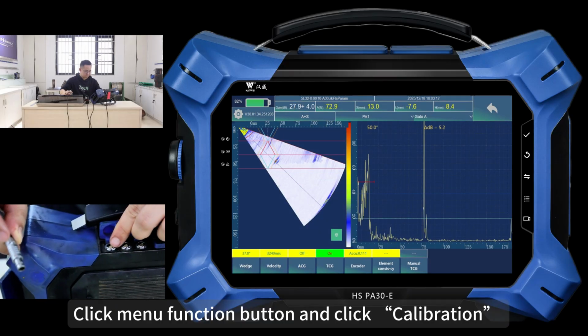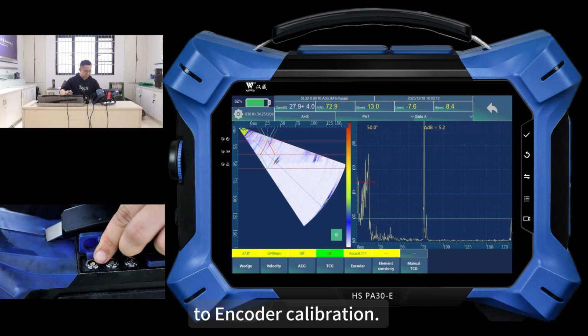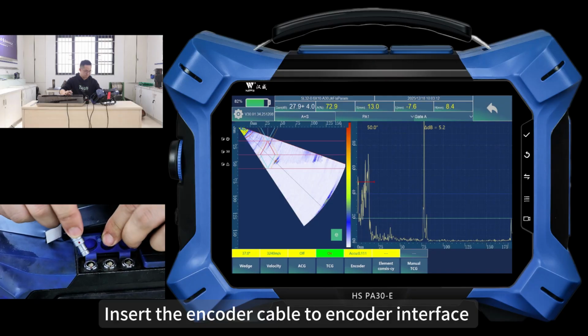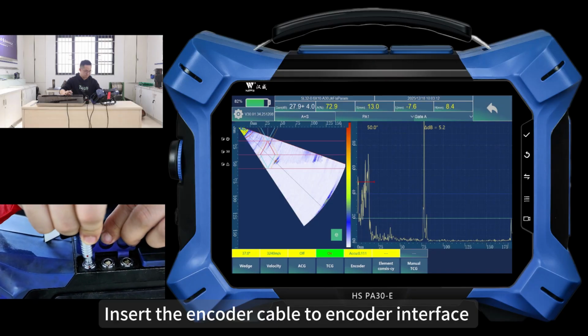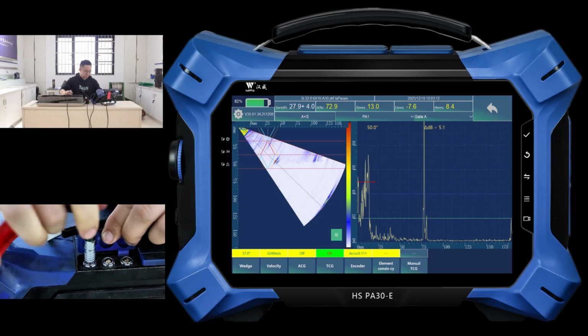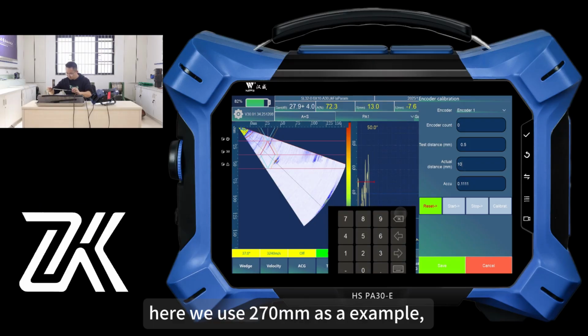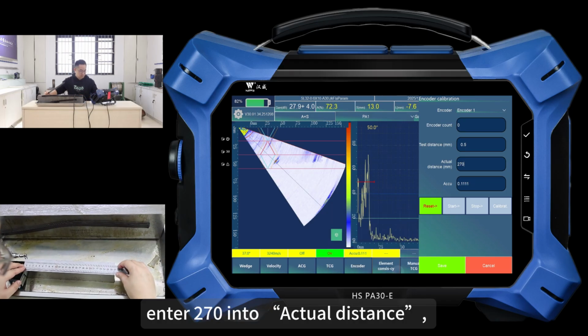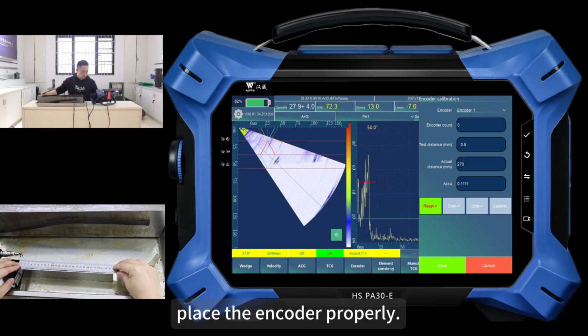Click Menu Function button and click Calibration to encoder calibration. Insert the encoder cable to encoder interface by red point to red point. Measure a distance. Here we use 270 mm as an example. Enter 270 into actual distance. Place the encoder properly.